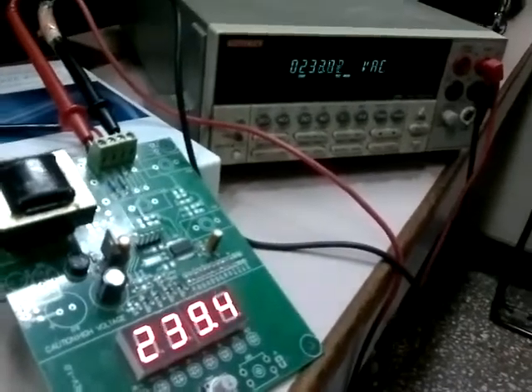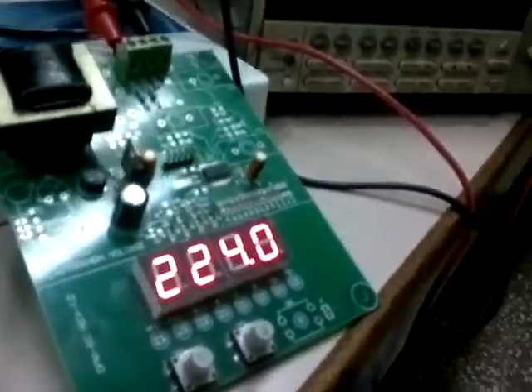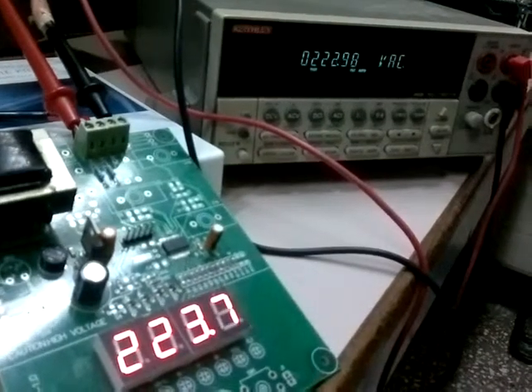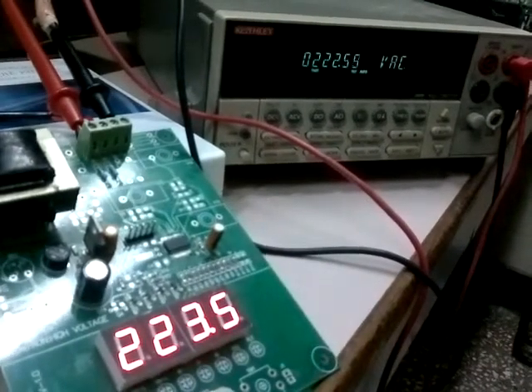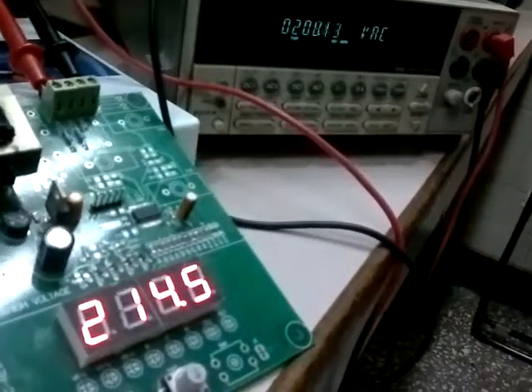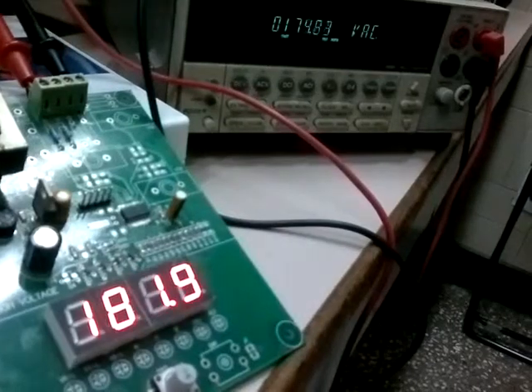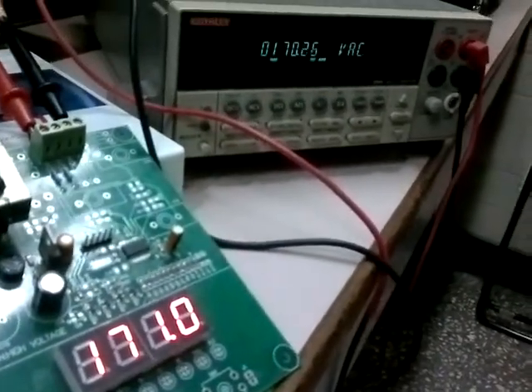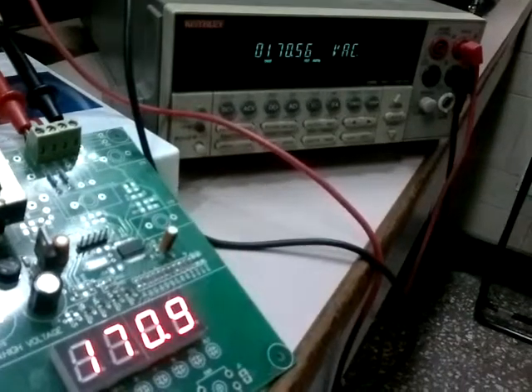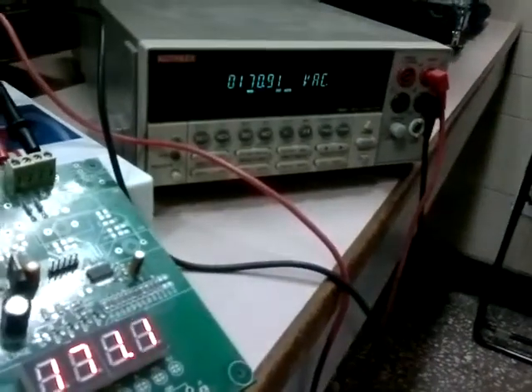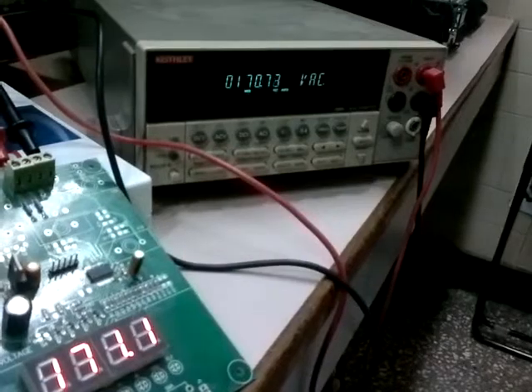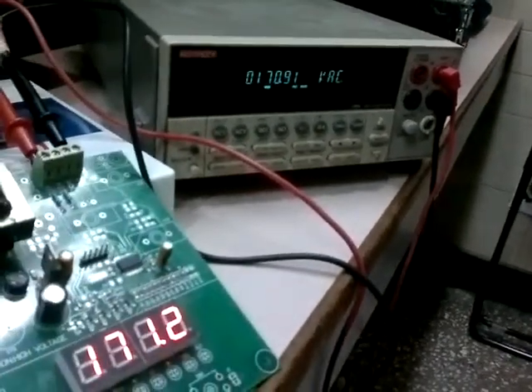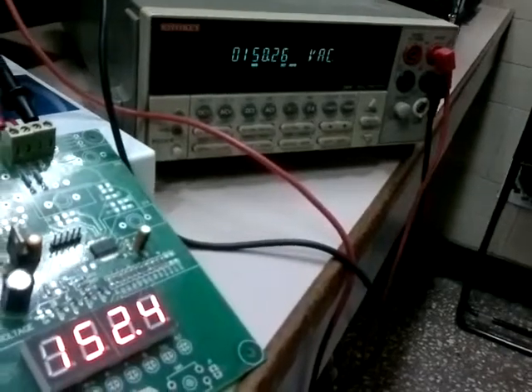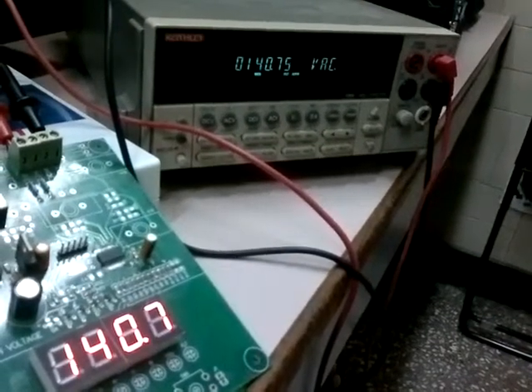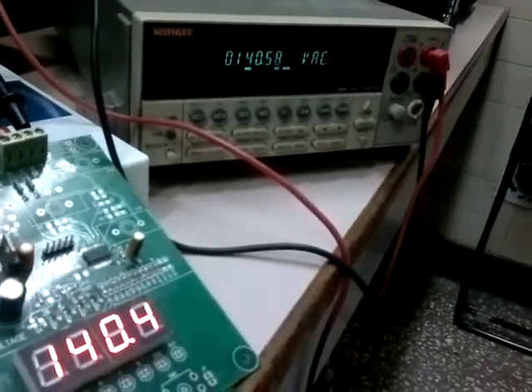I will reduce the voltage. Now this is 223, and you can see the meter is also at about 223.45. Let us go down lower. This is now 171, and so is the meter, reading about the same voltage. This should make it more stable on the meter side. I've increased its averaging. Now we can see that the DPM is tracking the meter nicely.